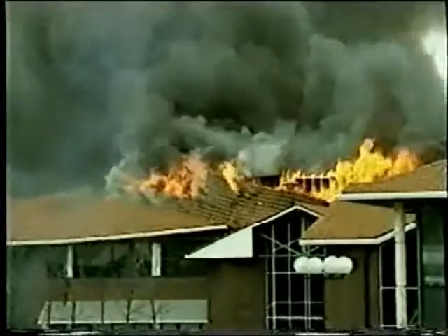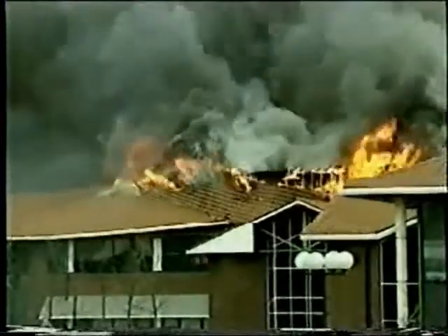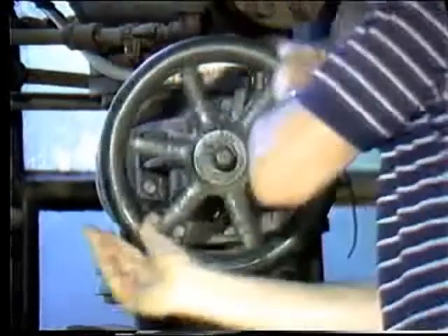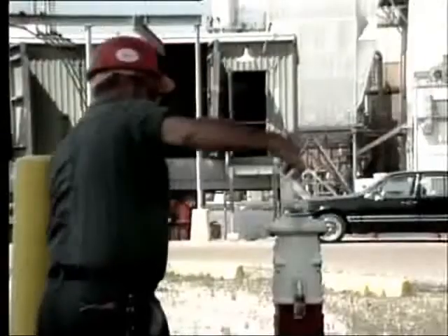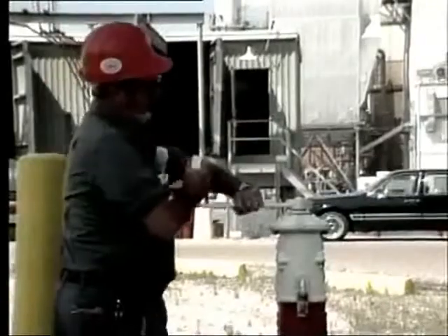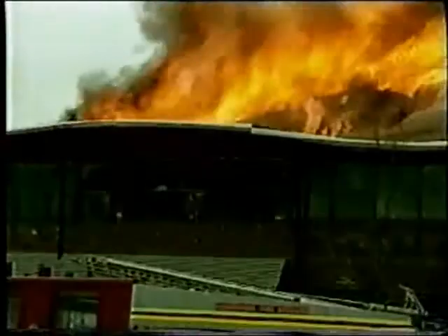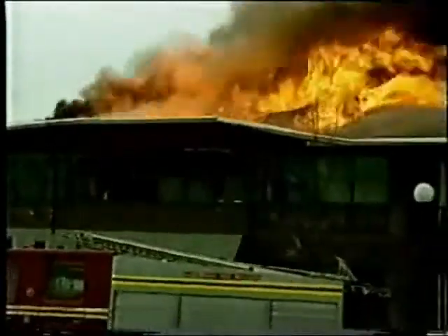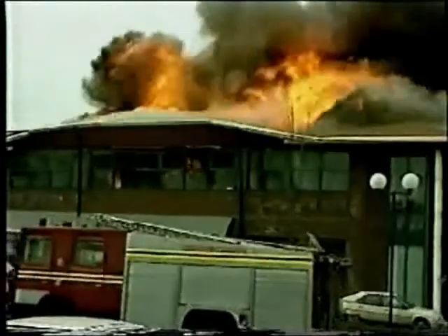First, there is the impairment to a system before a fire. The usual cause of an impairment is a partially closed or totally shut valve. Such improperly closed valves are usually a result of carelessness after routine maintenance or testing, or during building renovations. Remember, a fire may happen at any moment. By the time a sprinkler system can be restored to service, the unprotected facility has a greatly increased chance of devastating loss.